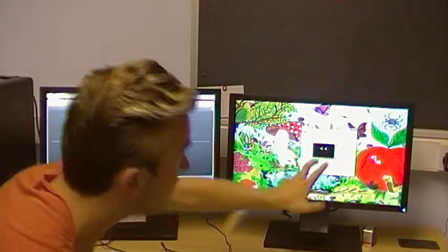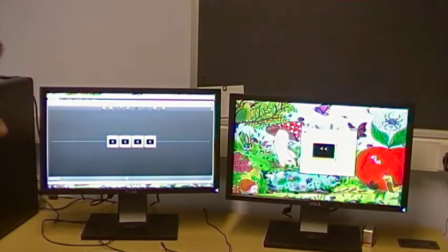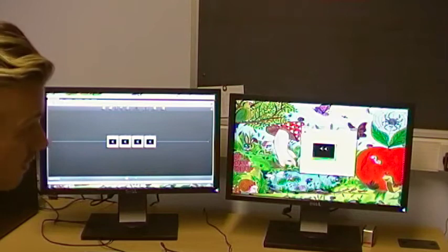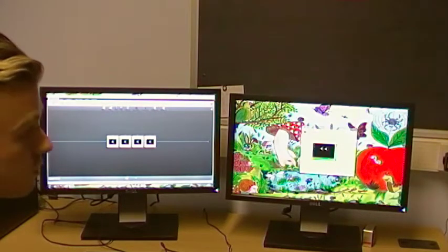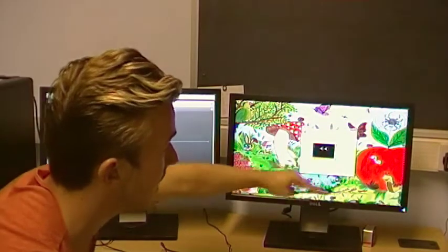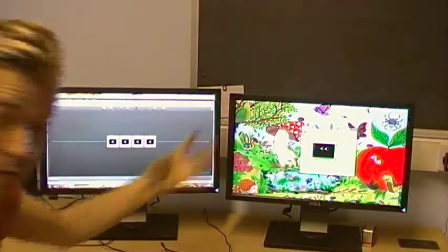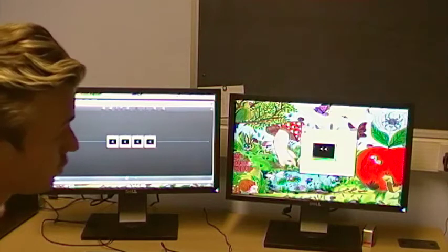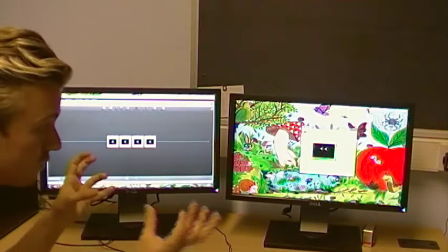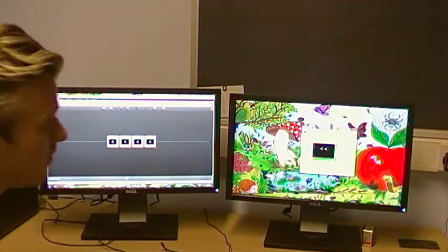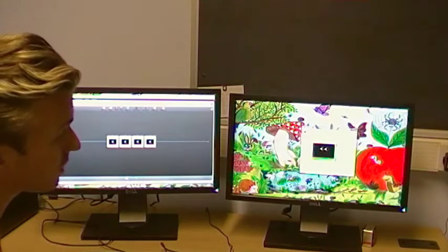And then you can see here those 2 dots are a representation of the pupils that the Tobii eye tracker is picking up, and you want those to be in the centre of the black box here and in the top third of the black box. So this here is perfect tracking really. This is your ideal, this is what you'd want your participant's eyes and track status to be before you start your experiment. And then you press start to begin.